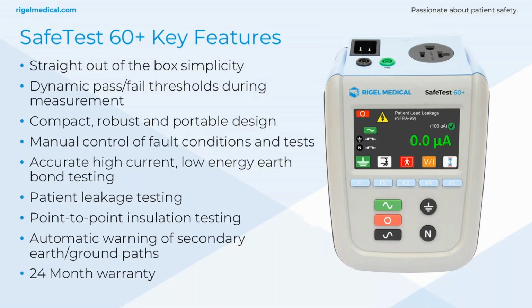One of the important aspects of the 60 Plus, our newest product, is that it's introduced dynamic pass-fail thresholds during measurement. This is just a great feature that ensures your results are inspected quickly. At a quick glance, you can see if the results fall within the safe limits of the code you're testing to. So it's a simple but effective tool for the specific requirements of any devices that you're testing. It will constantly measure those against the preset limits. So once you've fired the device up and assigned the specific test, it will give you the pass-fail feedback to help streamline the process.